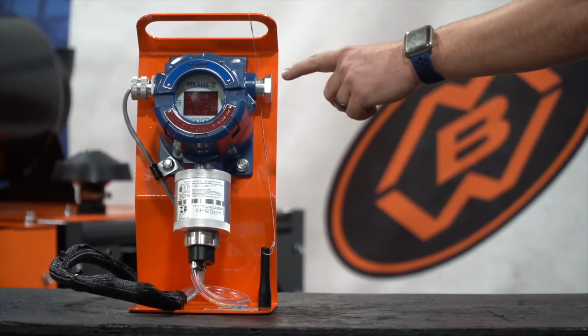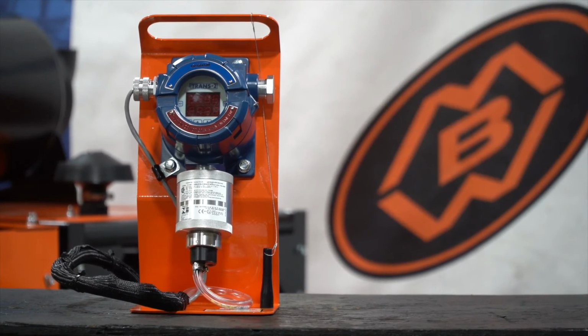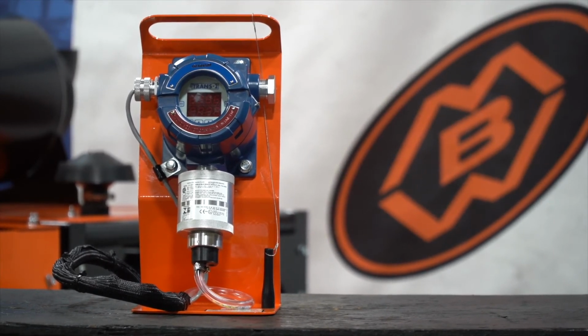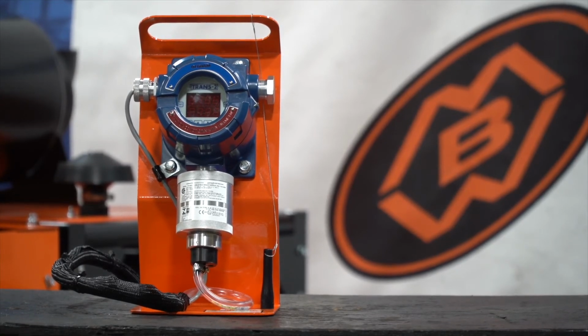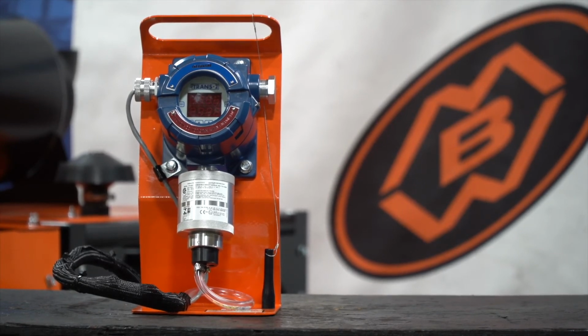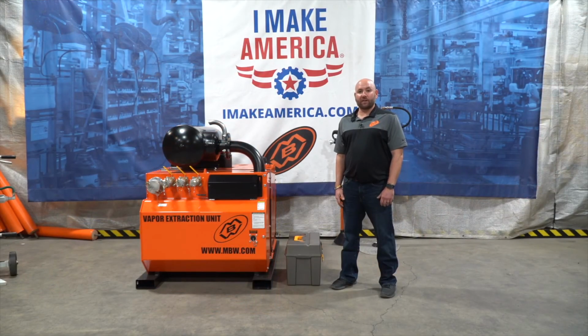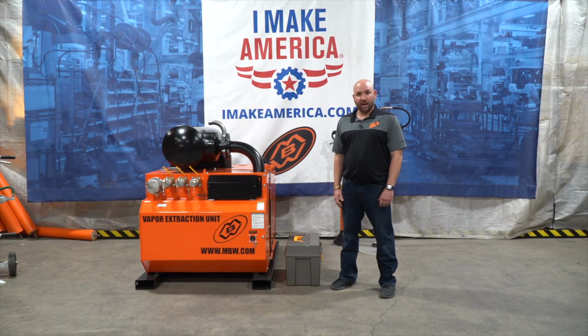This is the LEL sensor for the vapor extraction unit that monitors in real time what is going on within the unit. This is the safety feature that controls the LEL audible alarms at 35 LEL and 50 LEL. And now we're going to go into starting and running the vapor extraction unit.